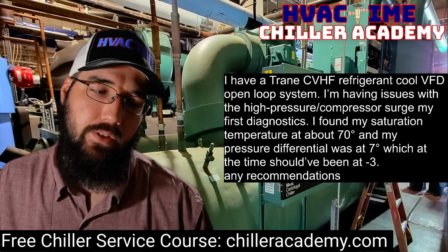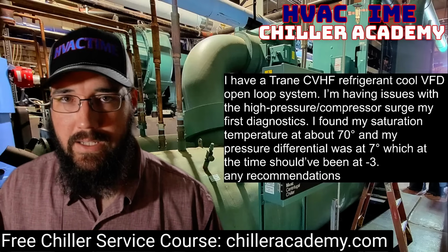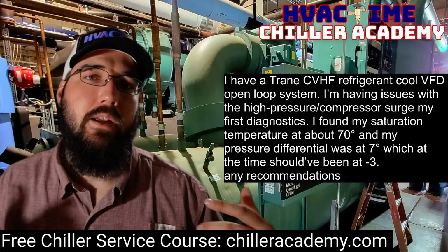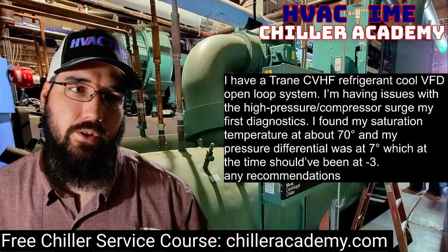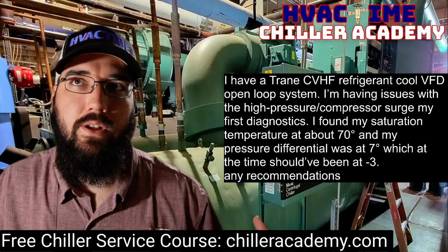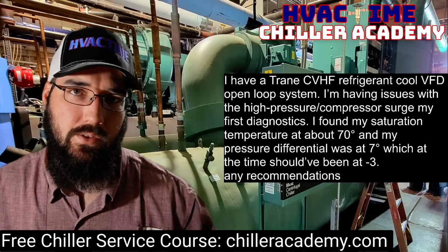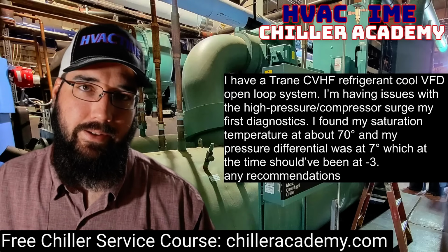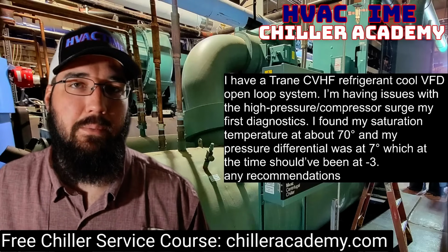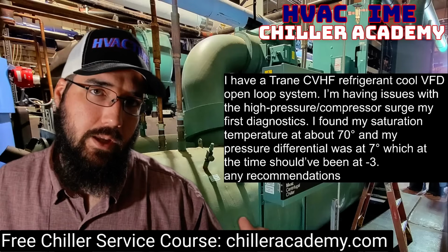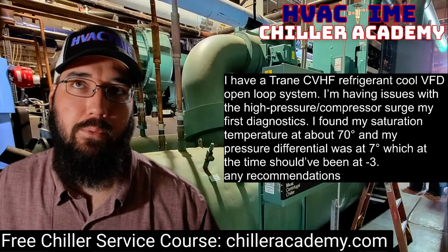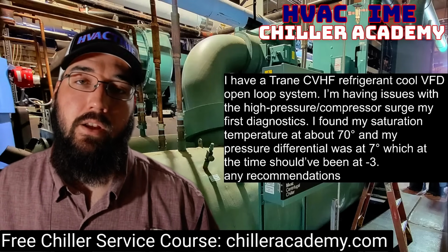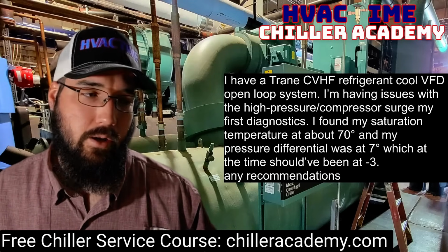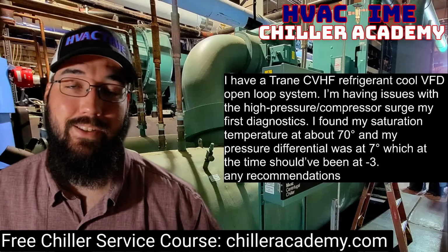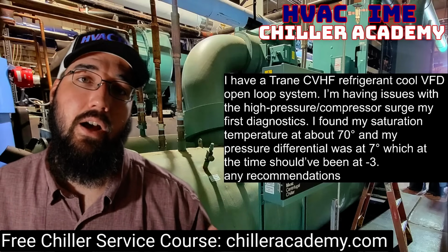If this was a seasonal, I'd give it a little more leniency, okay? If this is not a seasonal and this chiller has been online consistently in recent months, but now it's got all this atmosphere, why is that atmosphere there? So at that point, I would recommend doing a pressurization. Get a pressurizer, hook it up, pressurize that chiller, and leak search the heck out of that thing. Figure out what is the cause.